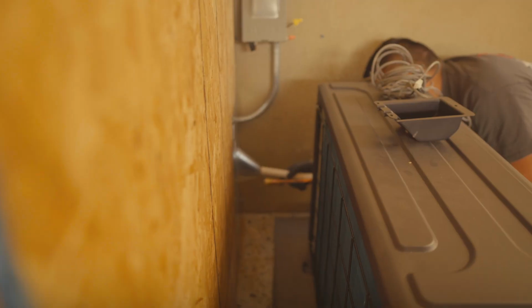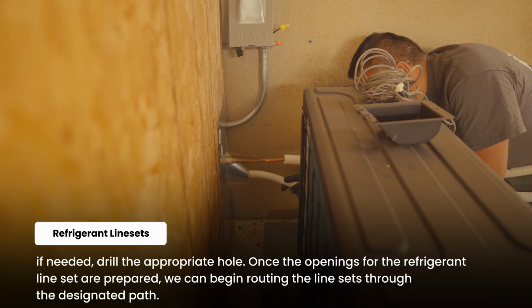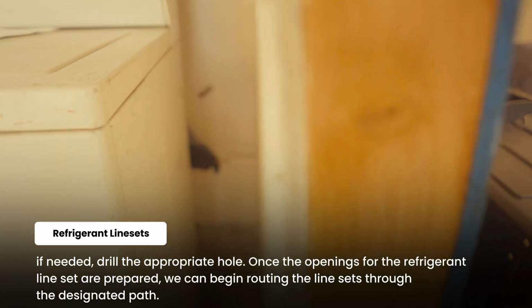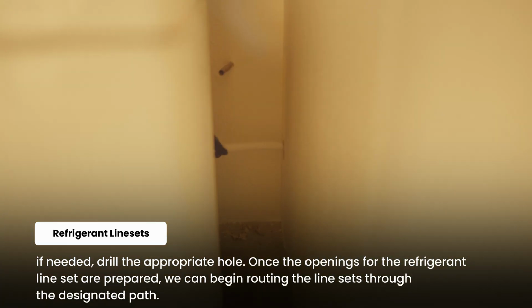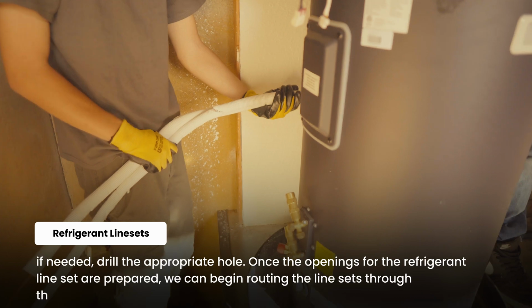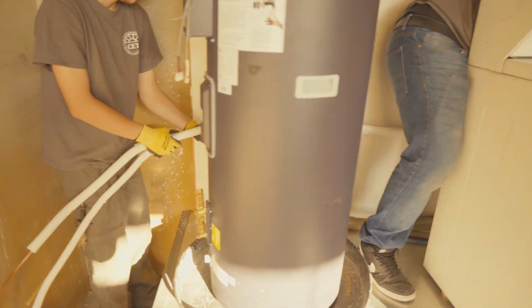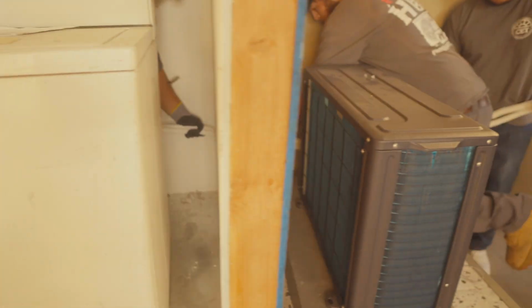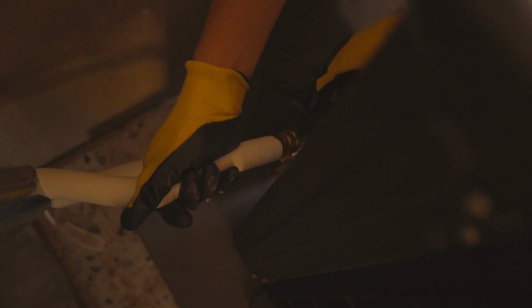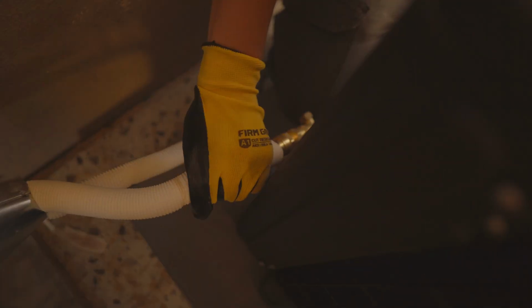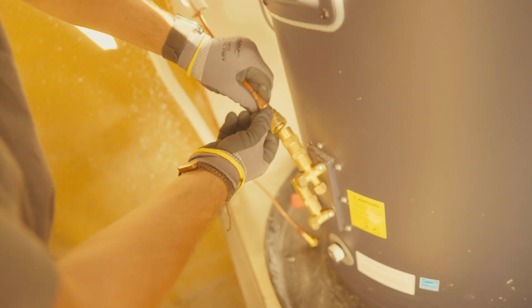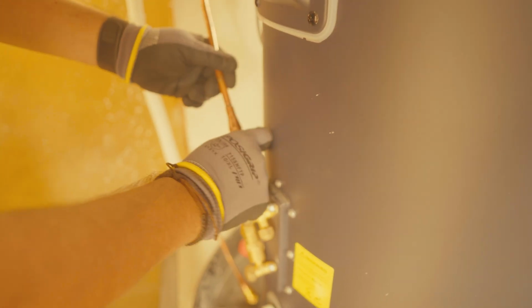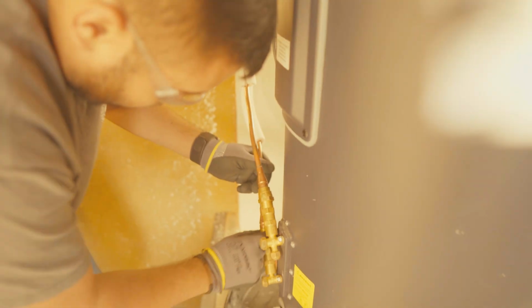Once the openings for the refrigerant line set are prepared, we can begin routing the line sets through the designated path. Next, we will connect the refrigerant line sets for the split system heat pump water heater. Start by attaching the line sets to the outdoor heat pump unit. Keep the line ends clean to prevent debris or moisture from entering the system. Then connect the matching line sets to the indoor water heater unit, completing the refrigeration loop.